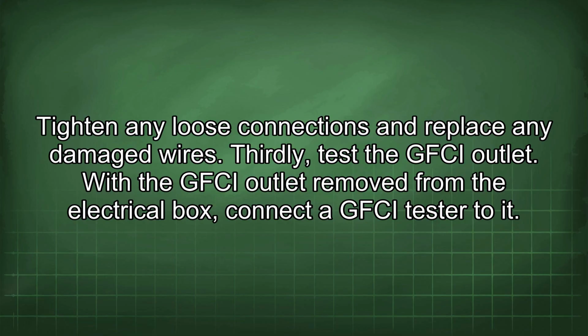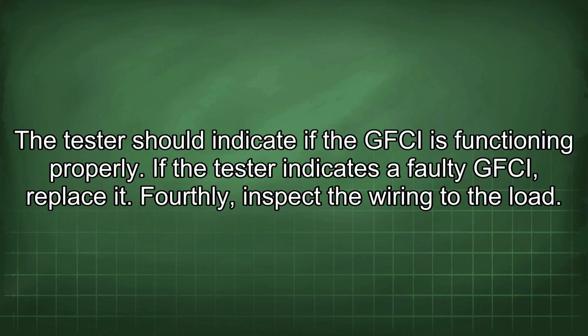Thirdly, test the GFCI outlet. With the GFCI outlet removed from the electrical box, connect a GFCI tester to it. The tester should indicate if the GFCI is functioning properly. If the tester indicates a faulty GFCI, replace it.